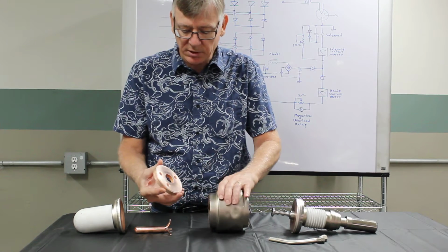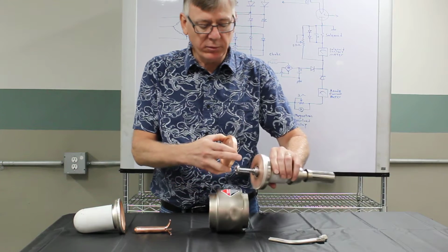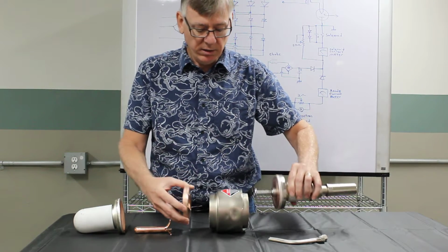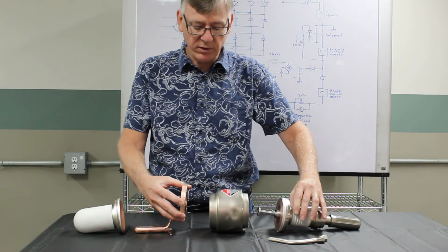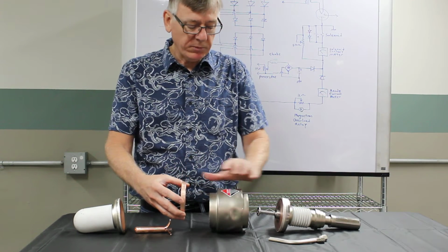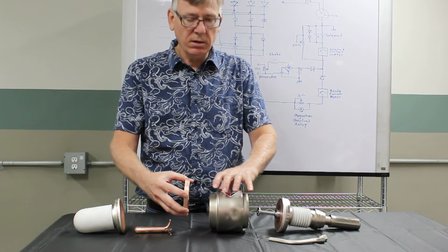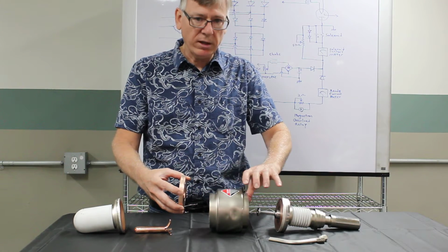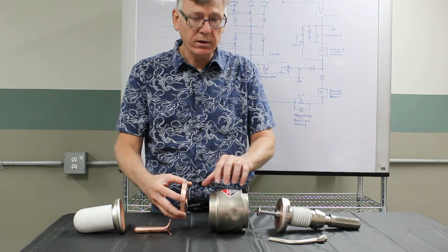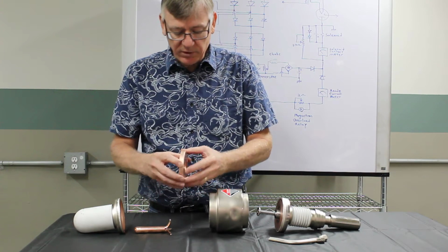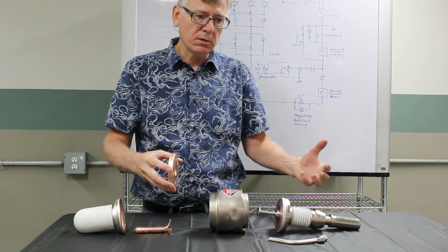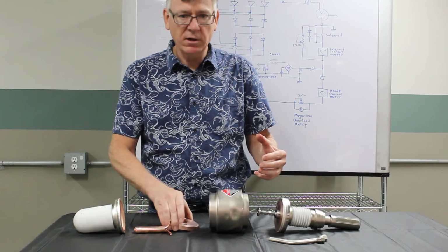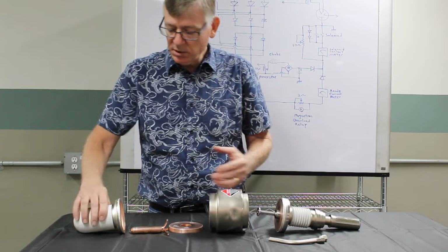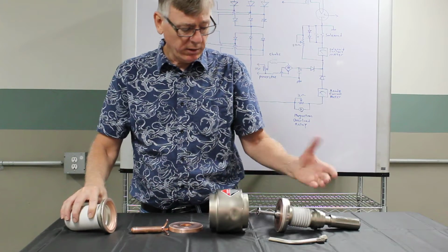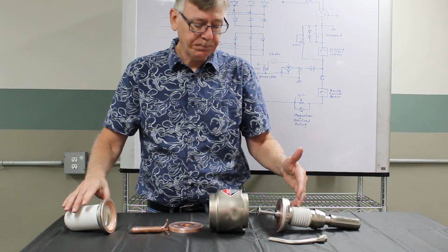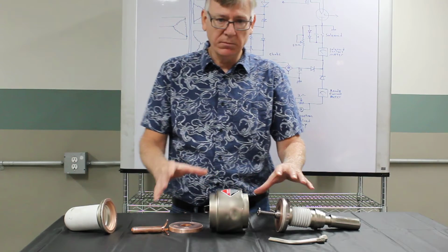So this part here is one of the pole pieces. This is an iron part. It's been copper plated, and the other pole piece has a steel ring on it. These make up part of the magnetic circuit, and they focus the magnetic field to stay concentric and in straight lines on axis with the center line of the tube. These couple with the external pole pieces, which are part of the solenoid assembly. One goes down at the bottom under the dome, and the other one goes on the outside, and that's what holds it into the solenoid. And so that's the magnetic circuit.